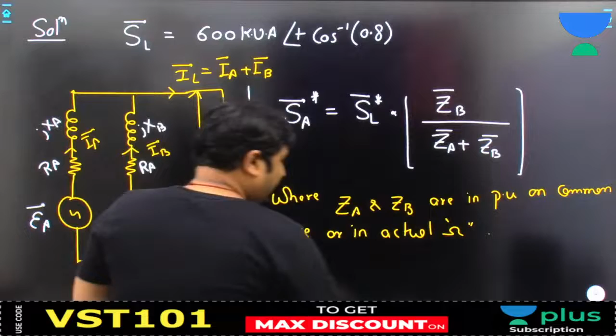Now please see. If you have to find the values, what is the value, beta? Please observe. Already we have ZA and ZB on their own base values. On their own base values is mentioned on the nameplate. So ZA is 0.01 plus j0.06. ZB is 0.02 plus j0.12. So put it in the formula to find the maximum kVA that this combination can deliver. Is it okay? Now please observe.